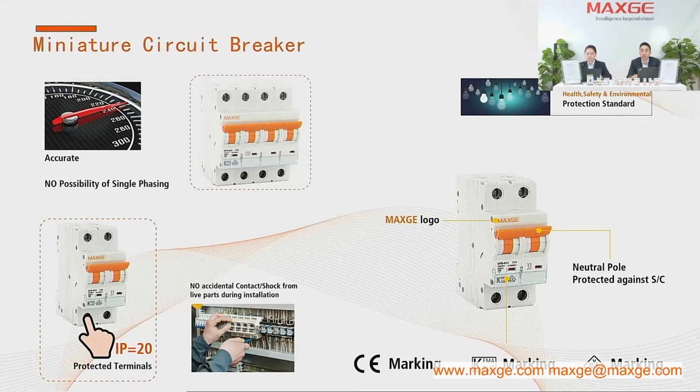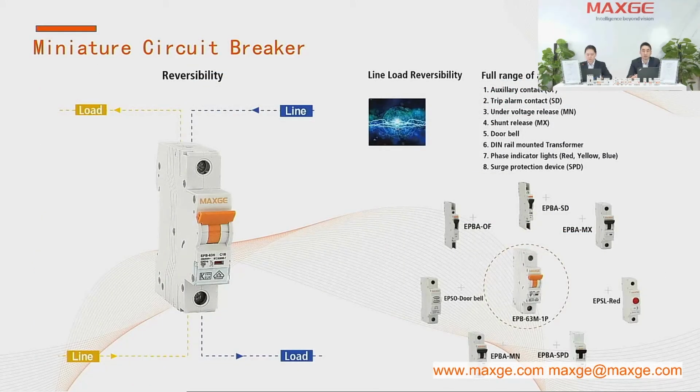Normally, the connection for the MCB during installation into the distribution box, it's line top side and load downside. But for some market, need the reverse connection during operations, means line downside and load top side. And it's for different markets and the customers' requirements. Our MCB can satisfy such requirements, and under such kind of connection, the performance will also keep stable. The MCB terminals are designed for IP20 protection, which keeps the safety during installation.